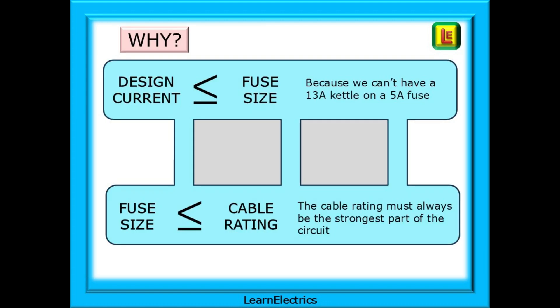Why does this matter? The design current cannot be greater than the fuse or breaker size. For example, we cannot have a 13 amp kettle on a 5 amp fuse. Every time it's switched on, the fuse will blow. And the cable rating must always be the strongest part of the circuit and chosen for its current carrying capacity for that particular circuit's installation conditions. It is chosen so that it does not exceed the limiting temperature before the protective device operates and to not exceed the voltage drop limit. It is easier to change a fuse than it is to rewire a whole circuit.